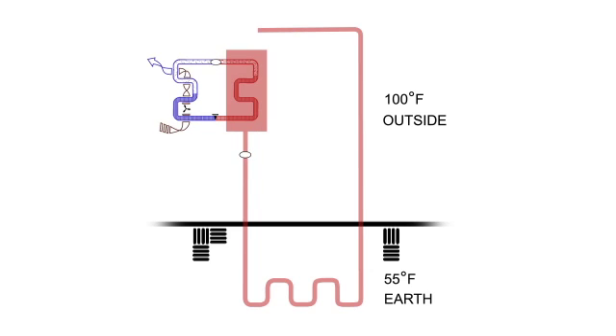The compressor simply doesn't have to create the level of high pressure required to condense in 100-degree air when the condenser is instead bathed in 55-degree water. In a geothermal system, then, it is said that we are utilizing the earth rather than the air as a heat sink.